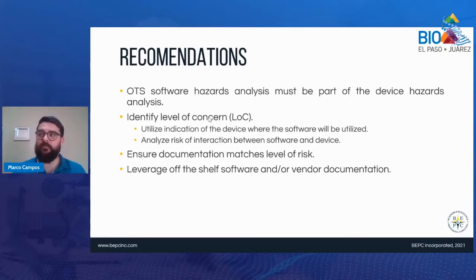Any type of device in the medical device industry requires a hazard analysis—what happens to the patient if something goes wrong with my device. It can be anything from minor bleeding to something as bad as potential death. So these two need to go hand in hand. You don't have your software and then your device separately. Your hazard analysis must cover both software and device.